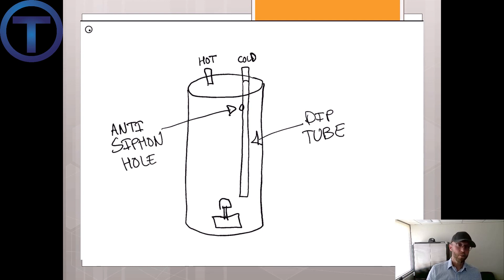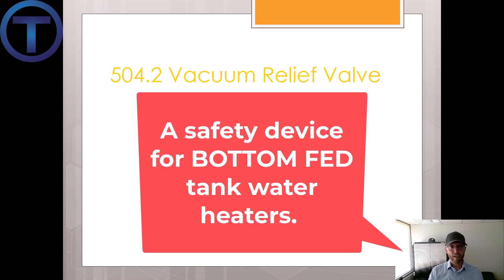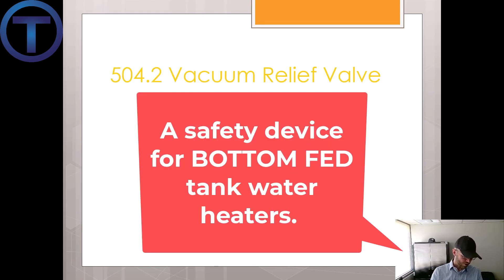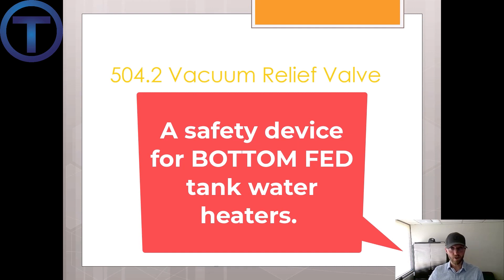504.2: a vacuum relief valve is required for some models of water heaters — particularly for bottom-fed water heaters. If the cold line comes in the bottom, we need a vacuum relief valve there.